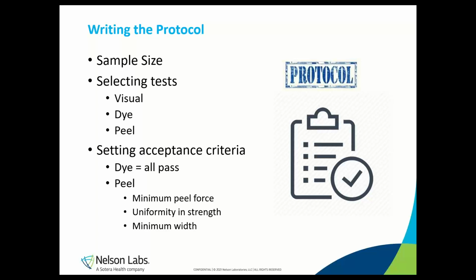We can pick a value based on experience or published data on the expected seal strength of the material. Or we can do some R&D on how changing the sealer variables affects the seal strength, as we discussed in the last slide. The objective of the sealer qualification is to show that the sealer can make good and consistent seals, not that we can get a certain seal strength number. We can create a product-specific minimum peel value for the packaging validation once we know what the typical values are from the sealer qualification. And then we can verify those values are sufficient to keep the package closed with the product during the packaging validation.